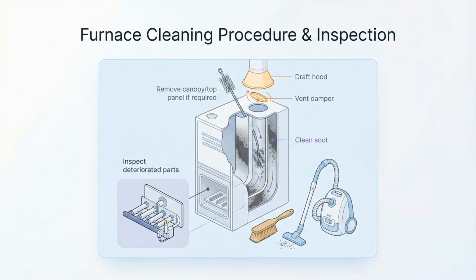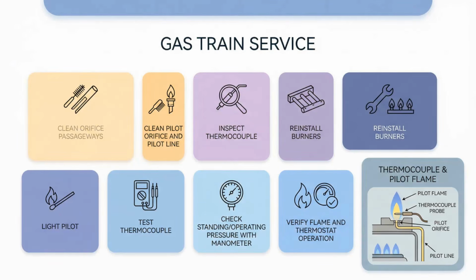Burners are cleaned gently, vacuum and soft brush, because damaging ports or components can create combustion problems. On the combustion side, service includes checking orifice passageways for blockage, cleaning the pilot orifice and line, and evaluating the thermocouple condition on standing pilot systems. After reassembly, the pilot is lit, the thermocouple is tested and replaced if needed, and standing and operating gas pressures are verified and adjusted if required. Then the boiler is restarted and flame and control operation are confirmed.